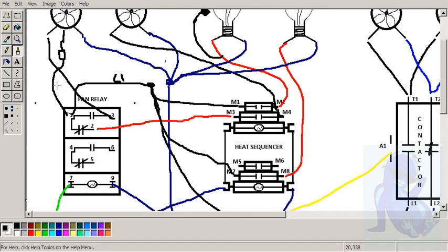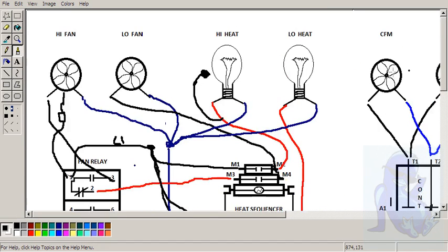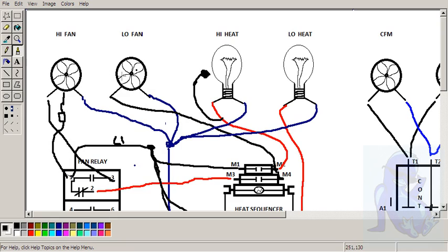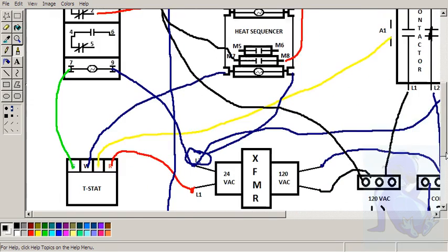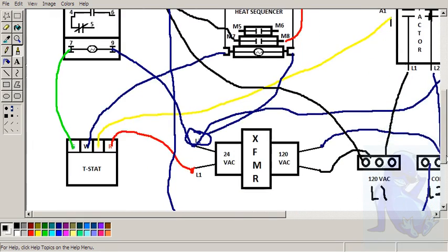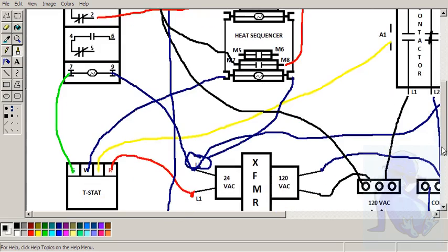You can put other safeties in there as well. You can put a safety on here that senses that, hey, if this fan's not running. If I don't sense air movement, this would be a special sensor just sensing the air flow. If I don't sense that air flow, I'm cutting off the power. I'm cutting off the heat. I'm cutting off these heat strips. There's so many different safeties. The safeties are normally closed. And they open up if there's something that it senses is wrong. It opens up, breaks the circuit. And then your system stops running.